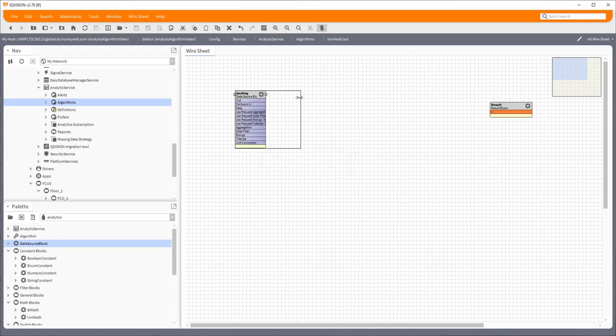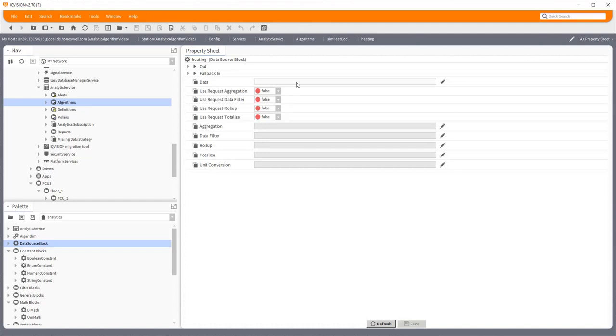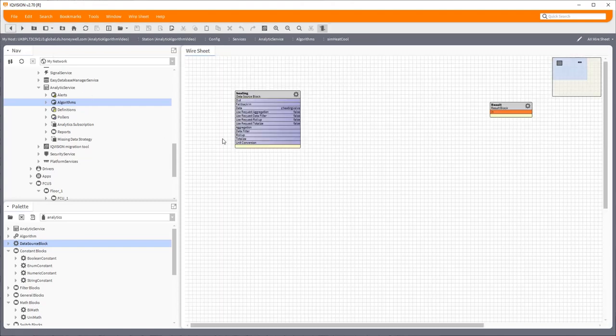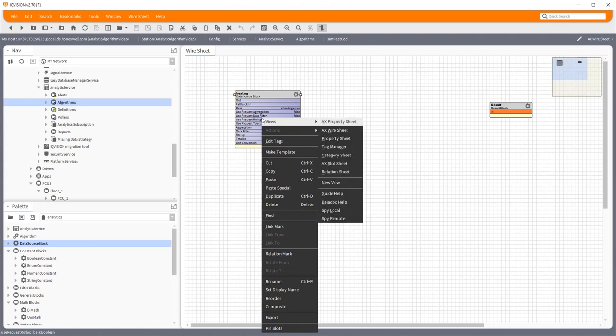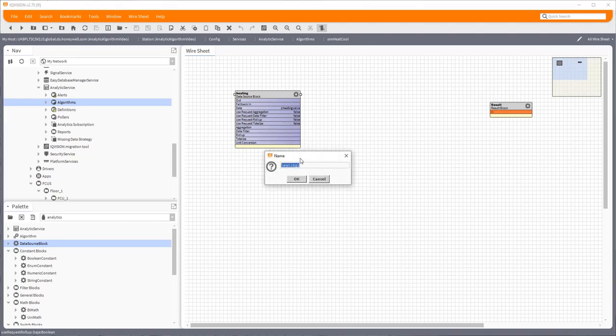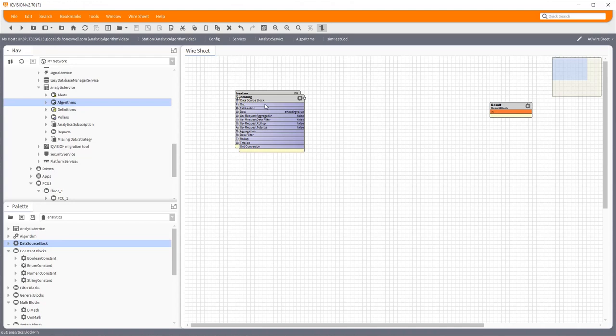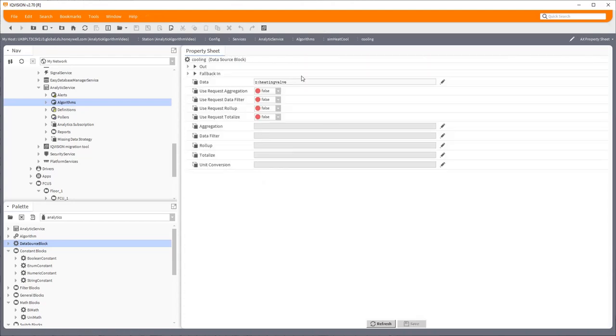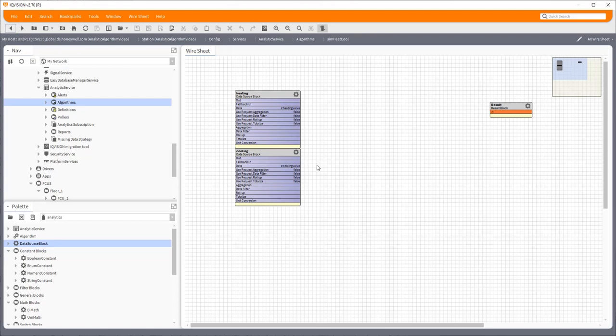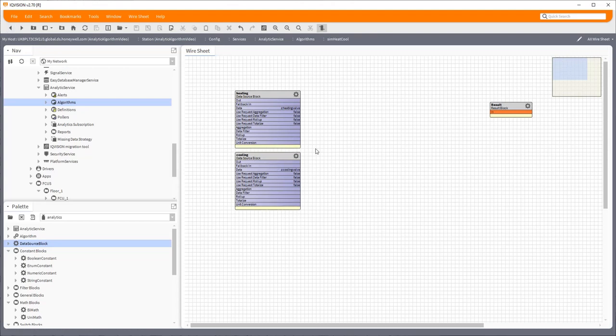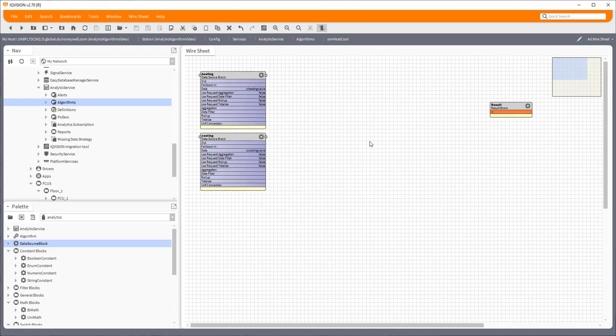So this is where we pick up the data we want to operate on. For us it's the heating and cooling valves, and it's always tag driven. So in here it will be heating valve, that's all I need in there right now so we'll just leave it that. Duplicate that one, and this one is obviously the other side of cooling. So that's our two source bits of data from the station. As I said, both driven by tags. Fairly simple, and it will just look everywhere in the station for these things.